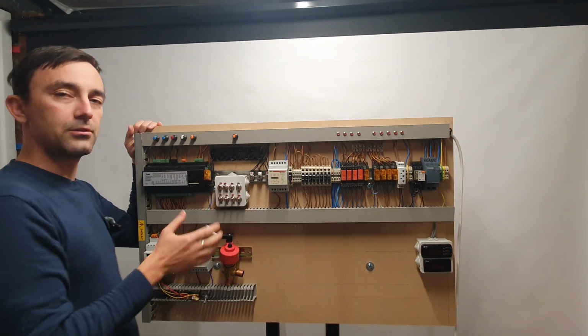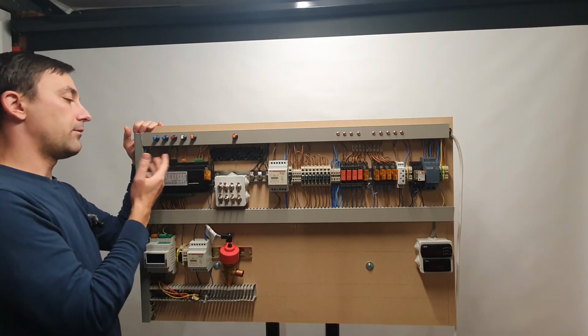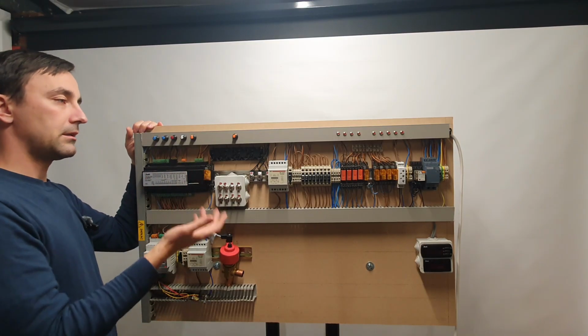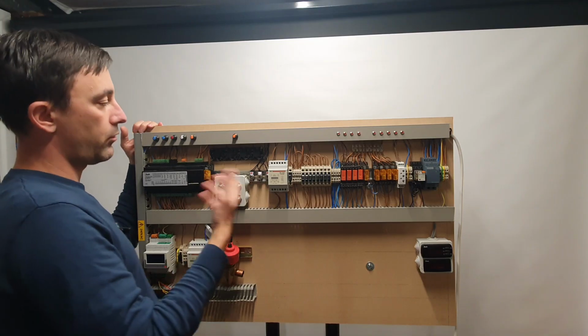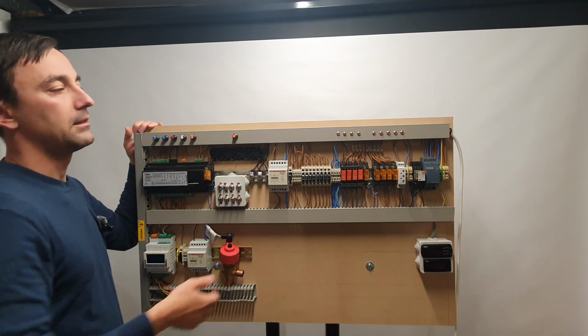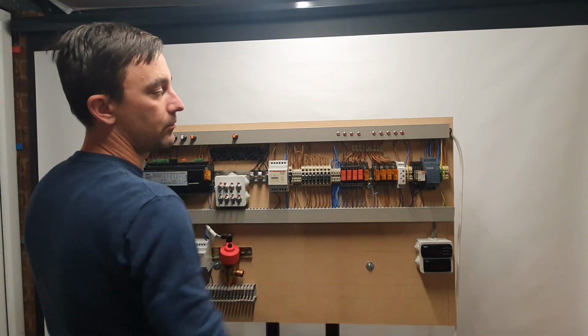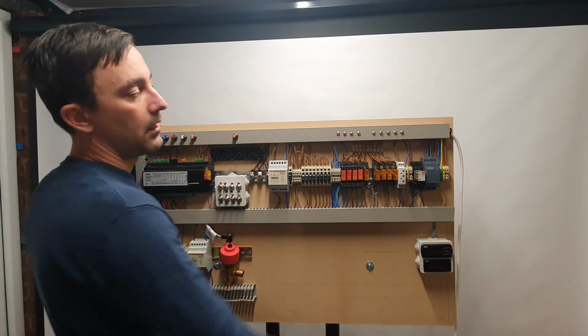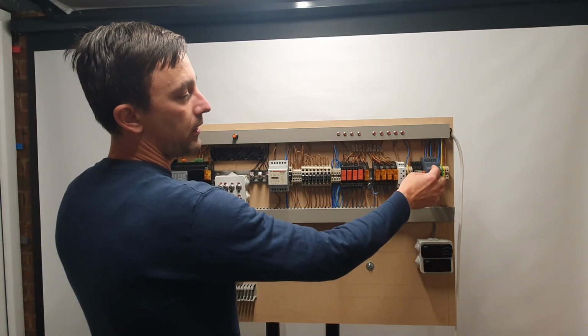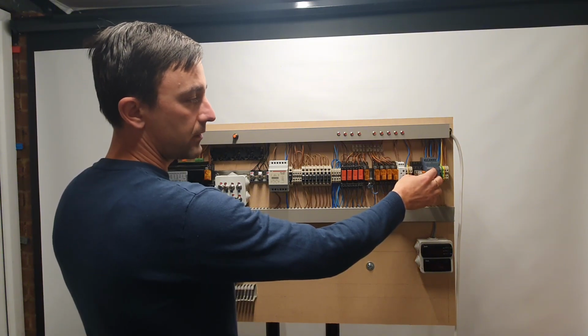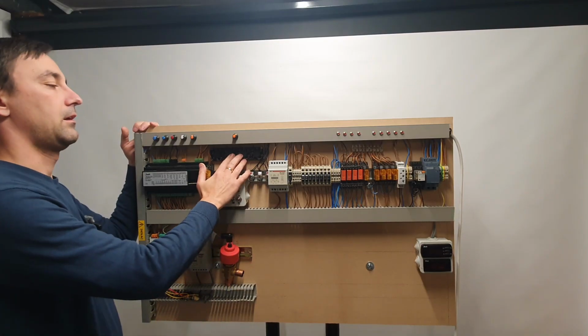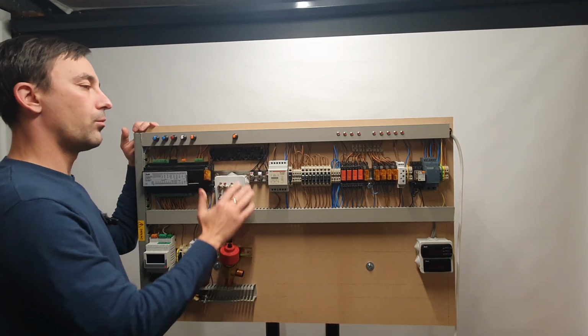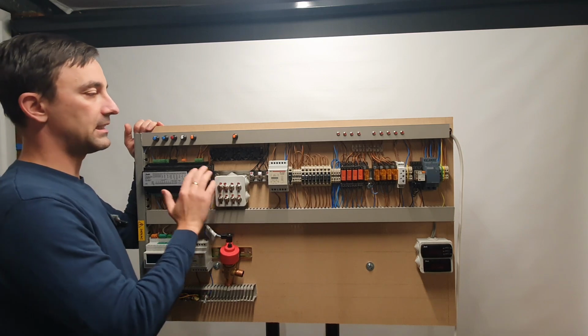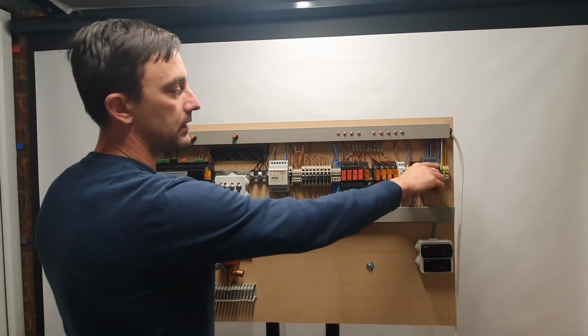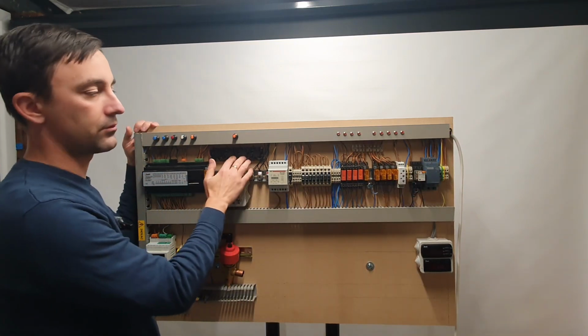So, but maybe in the future, if we do have a controller which can operate condenser fans as well in sequential mode, for example, then this relay will have to be in place. And moving on, we have a 12 volt DC transformer. It's because these fans run at 10 volts. So I had to use a DC transformer in order to run these 4 fans.